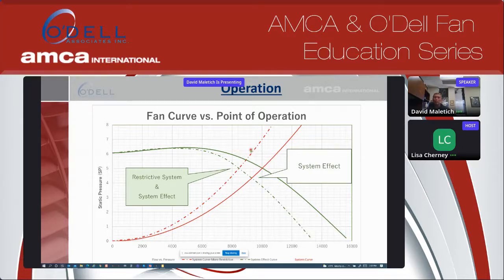If, for example, you take the bell mouth off, it becomes more restrictive and shifts the curve left. Put a bad hood on there, it shifts left. You close a damper on that, it shifts left. So that's a system effect curve. If you put a corkscrew on the fan, it's going to change the entire shape of the fan curve and change it to something that might look like this dotted curve here.